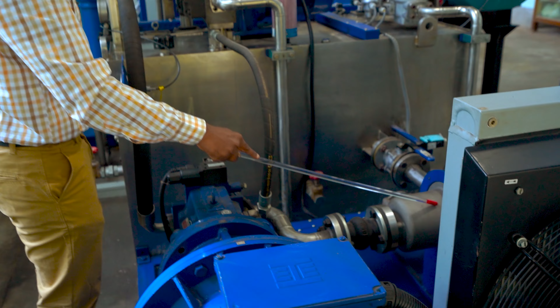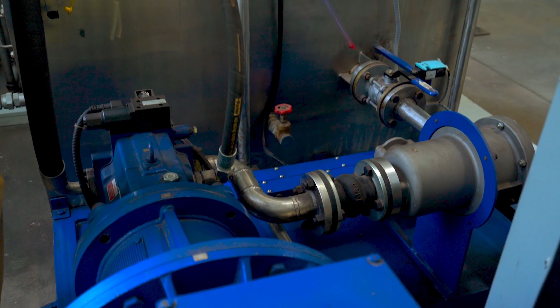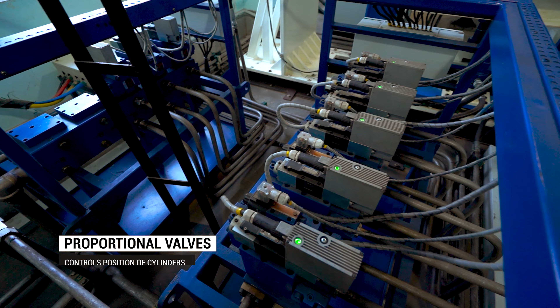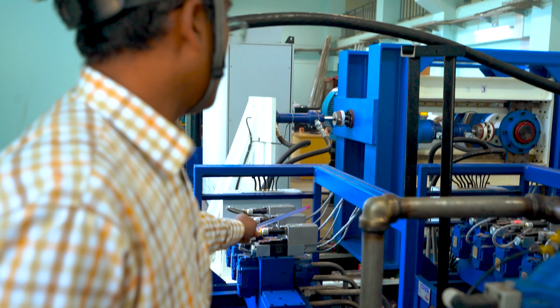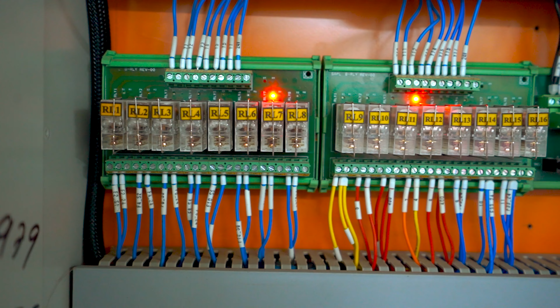Now even for the main pump, when the oil is coming into the hydraulic pump, it comes through a filter. So this filter is a 150 micron mesh size filter. So at all stages you are trying to remove the debris which is getting generated from the oil, because any sort of debris in the line can damage the proportional valves. So these proportional valves over here, they can be used to control the position or the load for the hydraulic cylinders, and the control of this is done using a PLC.